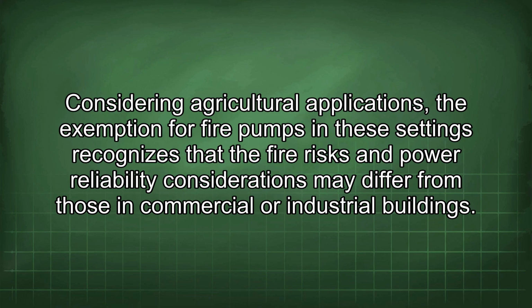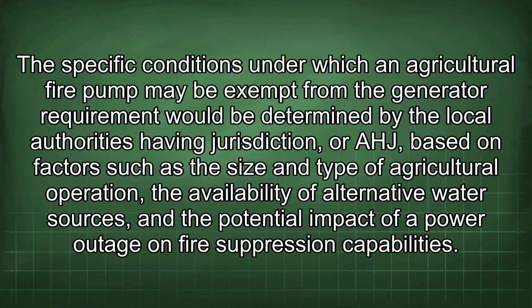Considering agricultural applications, the exemption for fire pumps in these settings recognizes that the fire risks and power reliability considerations may differ from those in commercial or industrial buildings. The specific conditions under which an agricultural fire pump may be exempt from the generator requirement would be determined by the local authorities having jurisdiction, or AHJ, based on factors such as the size and type of agricultural operation, the availability of alternative water sources, and the potential impact of a power outage on fire suppression capabilities.